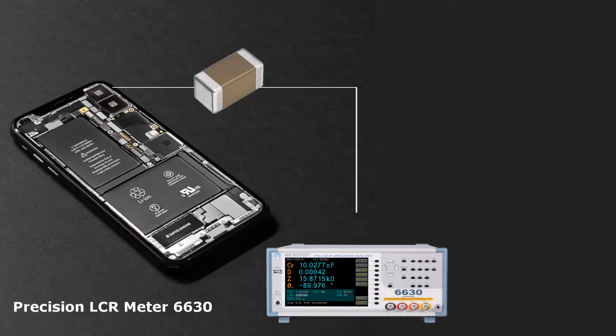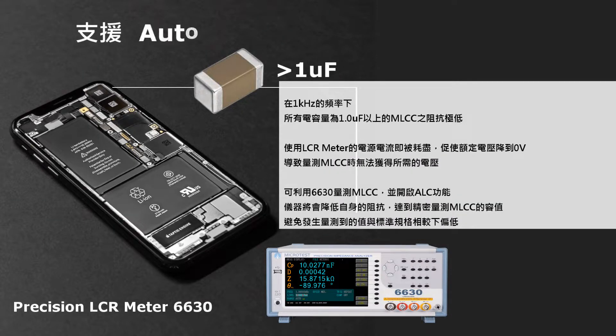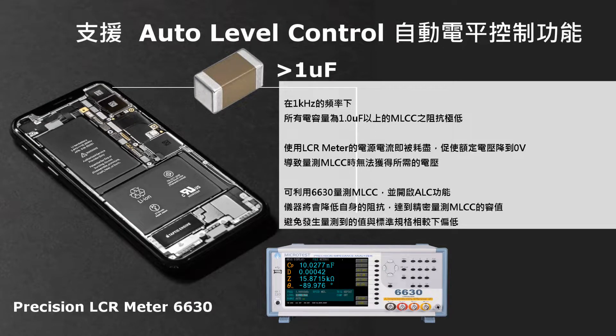For MLCC, the Automatic Level Control function is necessary to accurately measure capacitors with capacitance greater than 1 uF. Without this function, the measured capacitance could read lower than the real value.